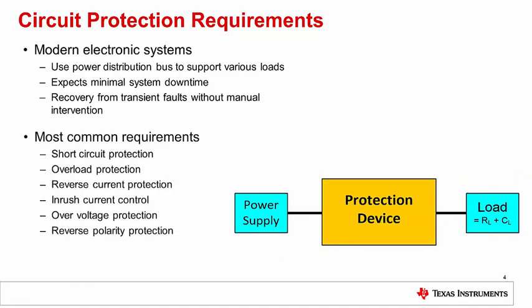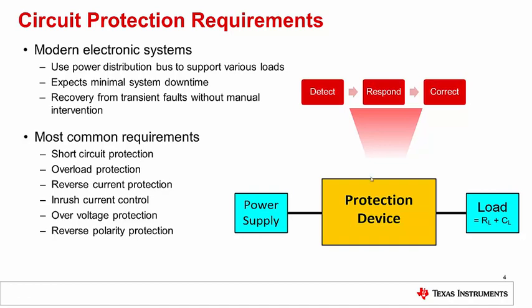Depending on the application, the protection device should provide protection against short circuit currents, overload currents, reverse and inrush currents, overvoltage and reverse voltages. The best way to prevent system downtime is to detect, respond to a fault, and correct potentially damaging conditions as quickly as possible, which means the protection device should provide active current protection.